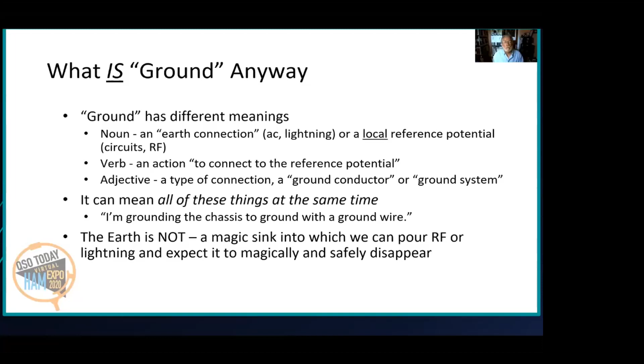Let's talk about bonding. Bonding is just a connection intended to keep 2 points at the same voltage so that everything goes up and down together. That's all it does. That's all it means. And that prevents shock hazards, which can be caused by voltage differences. If you have one appliance up here and something else is grounded down here and you happen to touch both points, you'll get a shock. So by bonding everything together, you keep your equipment's exposed metal at the same voltages, and that reduces the hazard from shocks. Destructive voltage differences can be caused by lightning surges. When a big pulse of current flows through a system, it can cause big voltage differences.